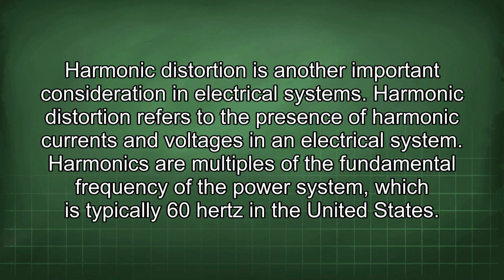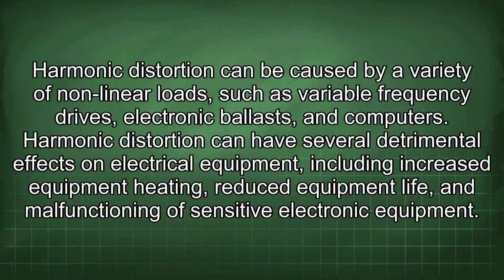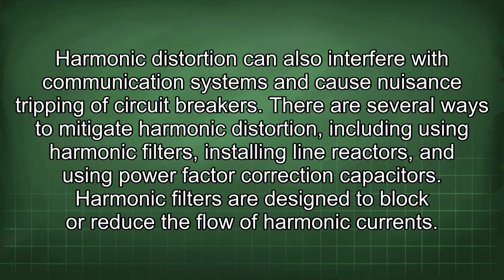Harmonic distortion is another important consideration in electrical systems. Harmonic distortion refers to the presence of harmonic currents and voltages in an electrical system. Harmonics are multiples of the fundamental frequency of the power system, which is typically 60 Hz in the United States. Harmonic distortion can be caused by a variety of nonlinear loads, such as variable frequency drives, electronic ballasts, and computers. Harmonic distortion can have several detrimental effects on electrical equipment, including increased equipment heating, reduced equipment life, and malfunctioning of sensitive electronic equipment. Harmonic distortion can also interfere with communication systems and cause nuisance tripping of circuit breakers.